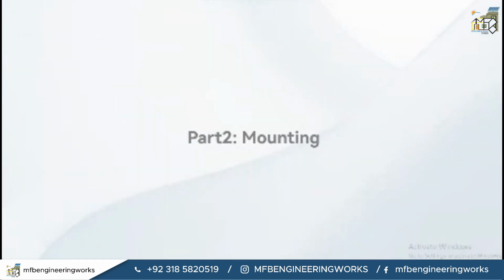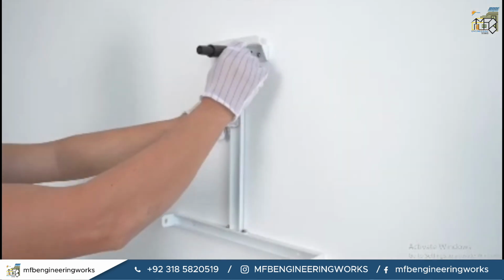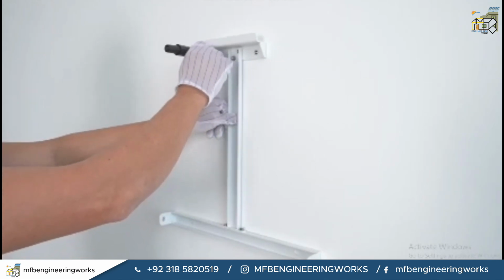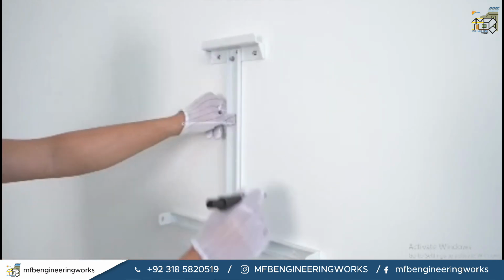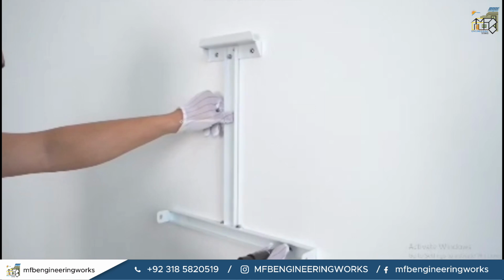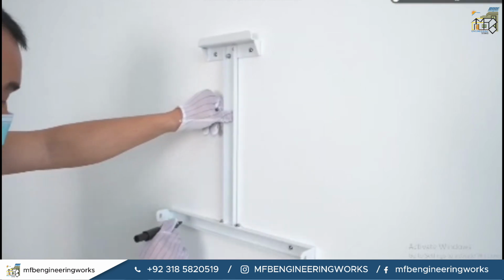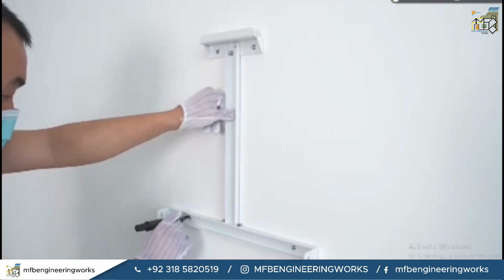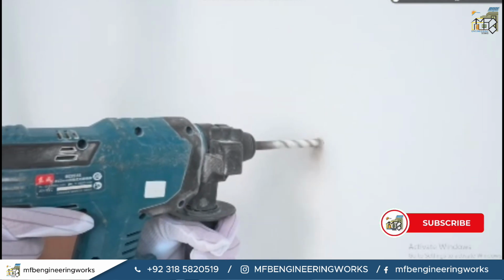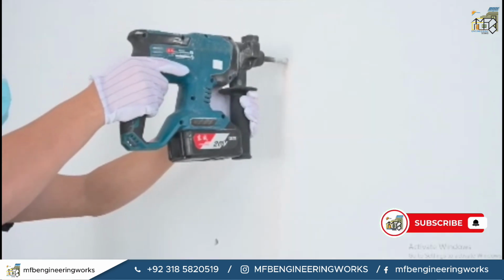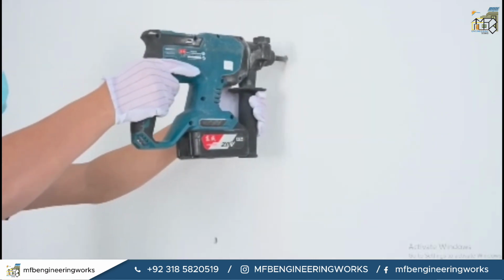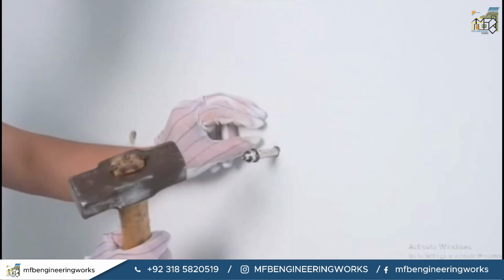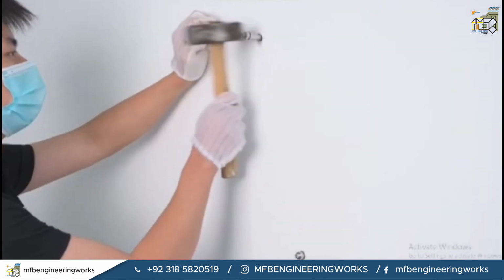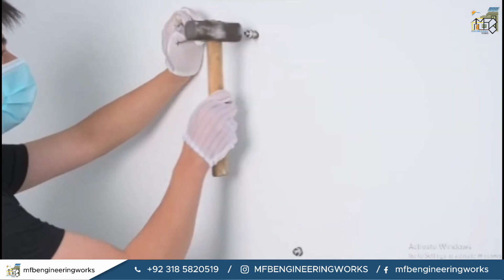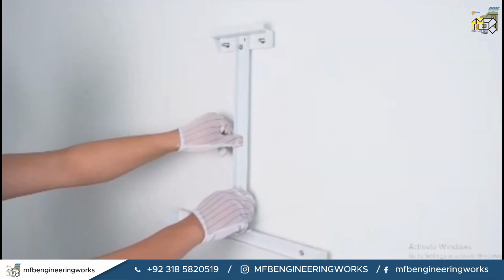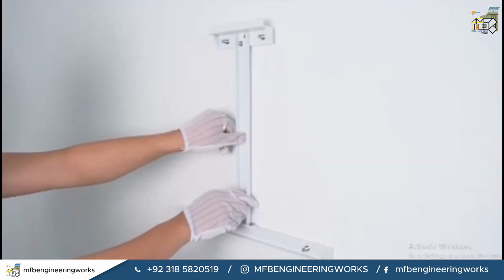While mounting the inverter, we first pick the wall bracket and place it on the wall to mark it, then drill holes using the drill machine. After that, we install the inverter on the wall-mounted bracket. After installing the inverter, we need to make sure that the screw at the side of the inverter, which connects the wall bracket with the inverter, aligns with the holes in the wall. And now we are placing the bracket.